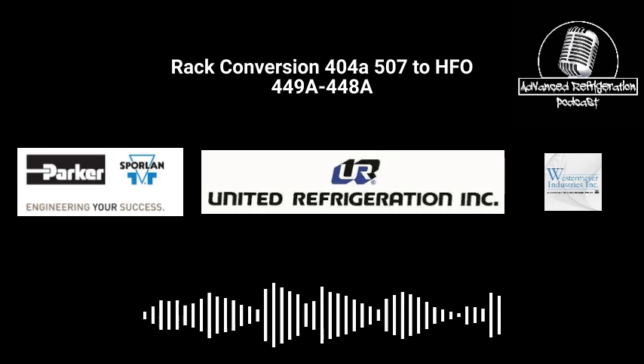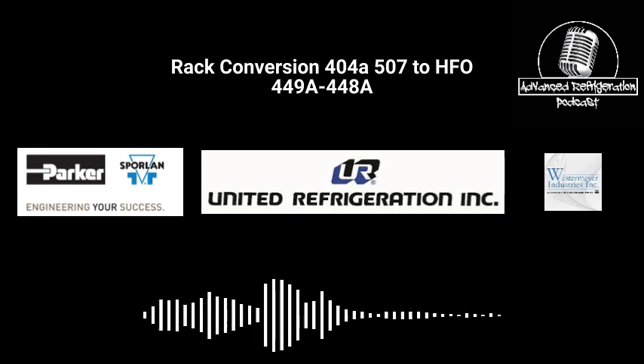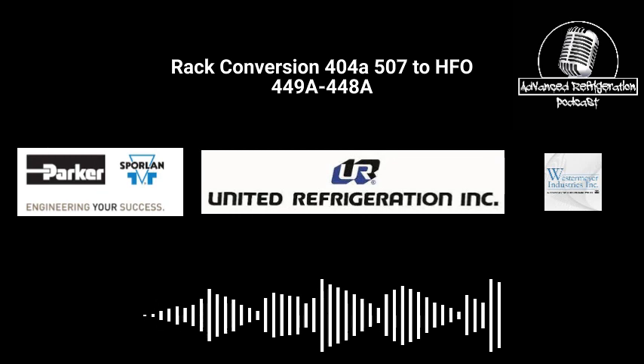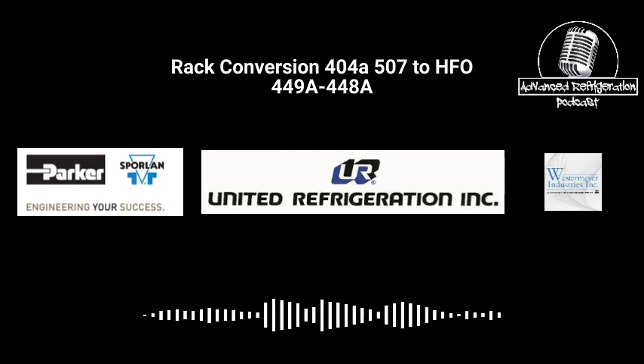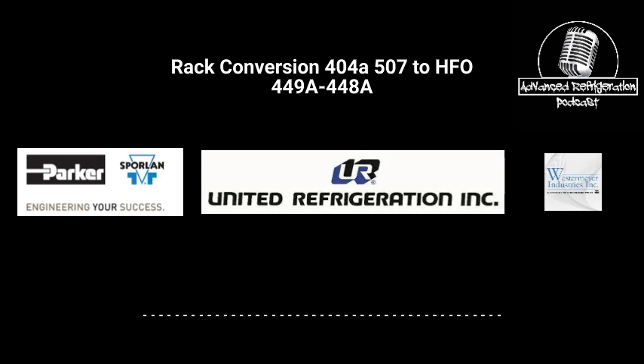That's it. I'm not doing anything else unless we have some ball valve we astronomically can't change. We're doing condenser ball valves before, all the ball valves before, because we can pump this thing down as many times as we want, do 2-hour stints and just knock it out. I don't want to do anything the night of the retrofit. I don't want this 2 a.m. scramble, panic attack. That's not good.